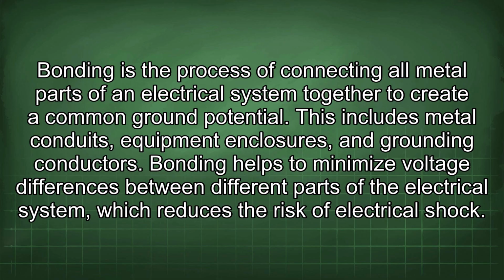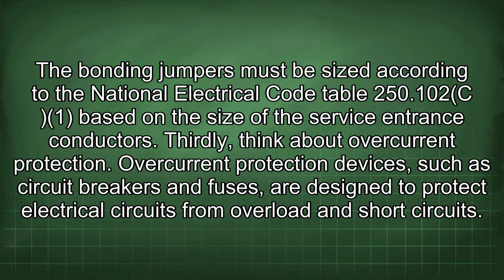Bonding helps to minimize voltage differences between different parts of the electrical system, which reduces the risk of electrical shock. The bonding jumpers must be sized according to the National Electrical Code Table 250.102(C), based on the size of the service entrance conductors.